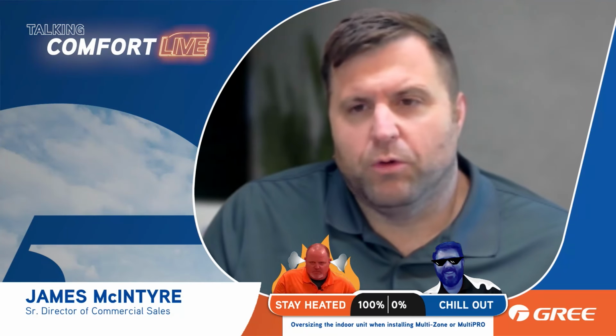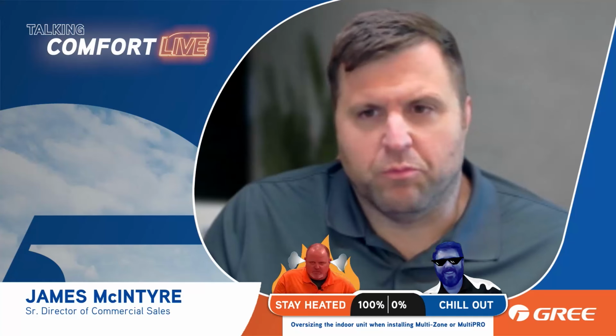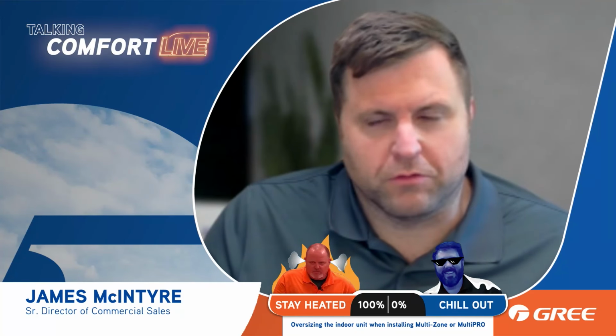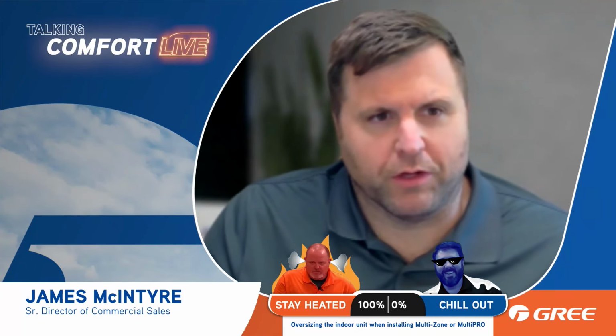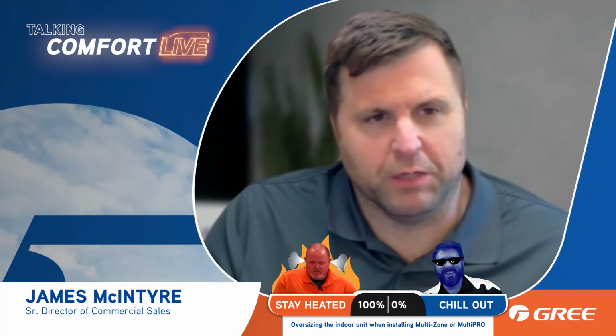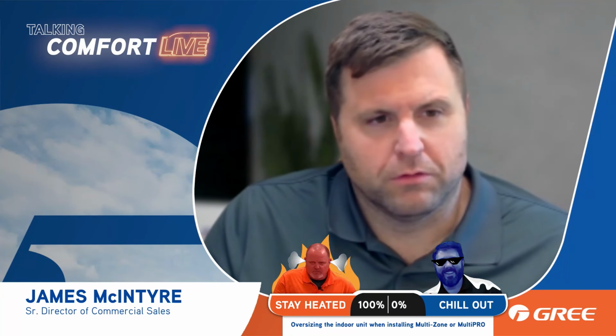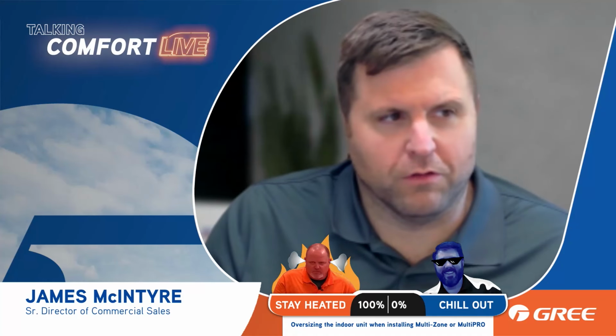In order to protect itself, it also has to have a minimum amount of run time, right? Because there's a certain amount of oil that we need to get back to the compressor. We can't run at a super minimum and then just shut off, and then run at a minimum and shut off, and so on and so forth.